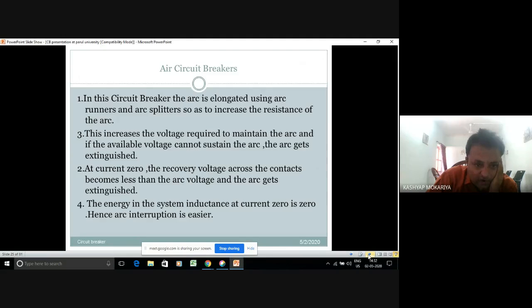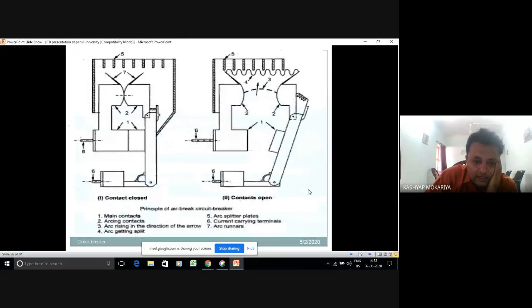This increases the voltage required to maintain the arc. At current zero, the recovery voltage across the contact becomes less than the arc voltage, and the arc gets extinguished. But it is important to see from the figure. From the figure you can see that number 2 is your arcing contacts. This is your arc runner, number 7. I have already told you before starting this presentation that I will send you all individual videos of all the breakers through Hital madam. While seeing this construction, you will get the video also, and the doubts can be cleared. You will see here some arc plates. What they are doing here, you can see, is lengthening the arc.